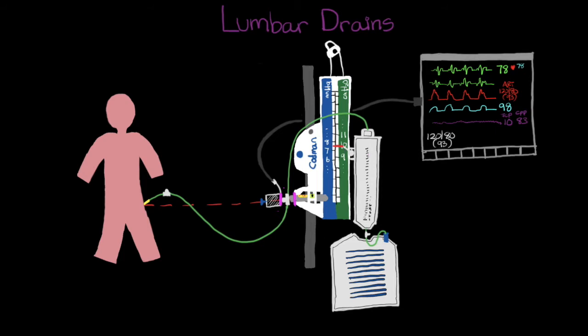And the purpose for this is you'll be able to see trends. So even though the number isn't going to be accurate, you will be able to see trends if the values are increasing. So instead of being completely oblivious to whatever the pressure is until your next hourly check, you will be able to see that increasing pressure, and you can come in and spot check what your pressure is periodically if need be.